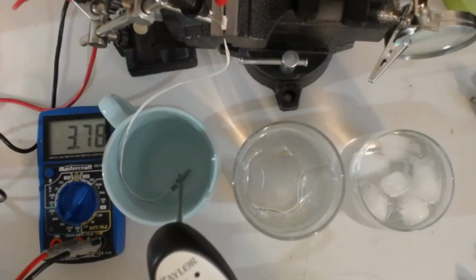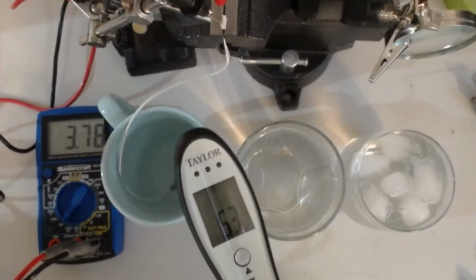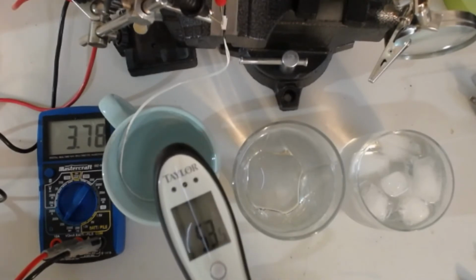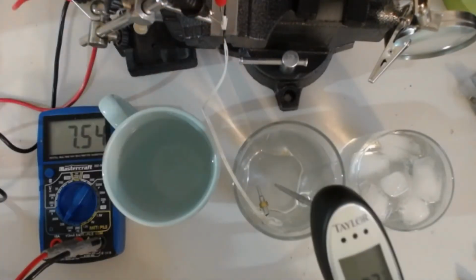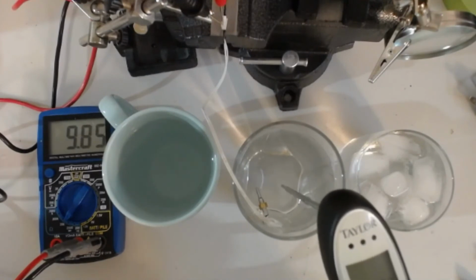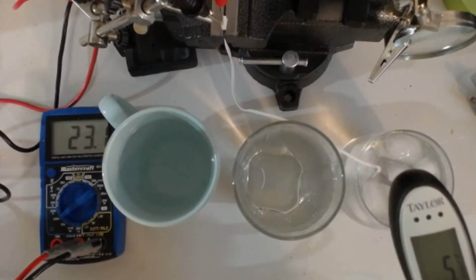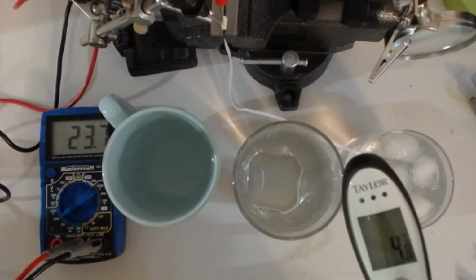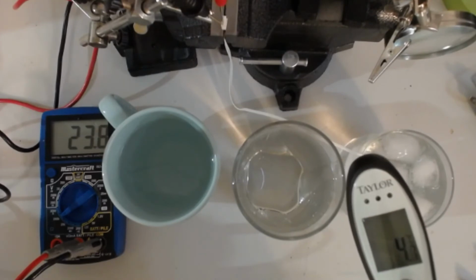Here's a demonstration of what the thermistors at the top and bottom of the heater do. When put in 50-degree water, the resistance is about 3.8 kiloohms. In 25-degree water, the resistance is about 10 kiloohms, and in ice water, the resistance is about 24 kiloohms. Lower temperature means more resistance. The microcontroller reads the resistance to determine the temperature of the probe.